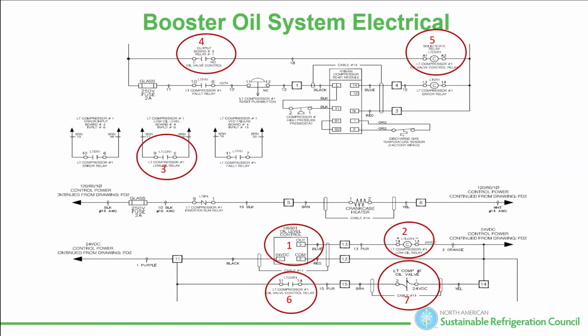Why? All right. So now let's say I'm coming into here and all I know is my compressor's off on oil. Where am I going to start? I'm not going to start at the switch necessarily. I'm going to start at the solenoid, because that's what's not coming on to feed oil. So me personally, what I do is I'm going to, again, put my meter on T2 or L2, and even on DC, I put it on the negative part of the DC. That's a negative voltage. It's not going to be like a neutral or whatever. And so I'm going to go on the other side.